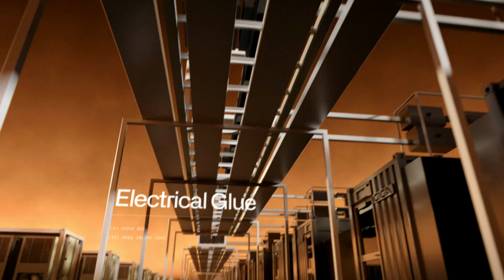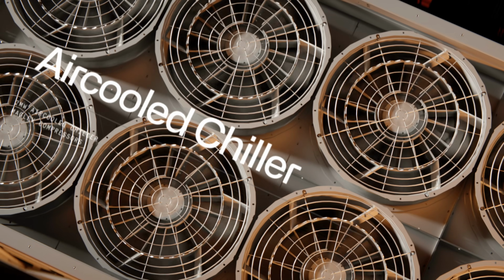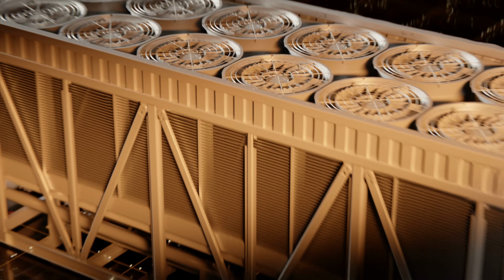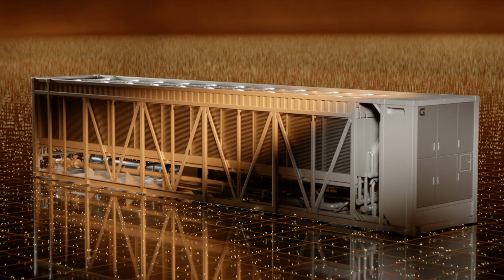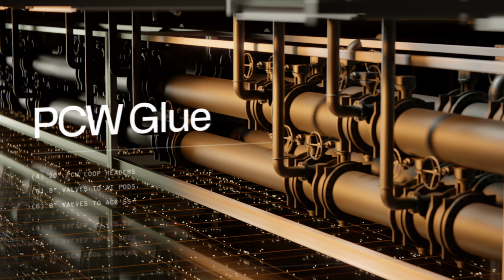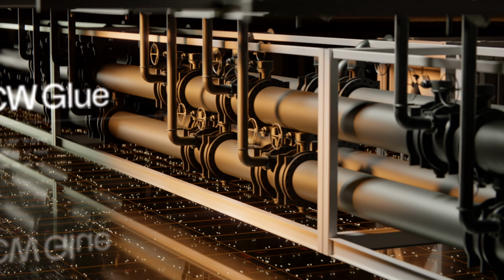The electrical glue module ties power distribution across the system. In the cooling chain, the air-cooled chiller manages heat rejection with maglev compressors, as the cooling glue module delivers temperature control for each AI pod.